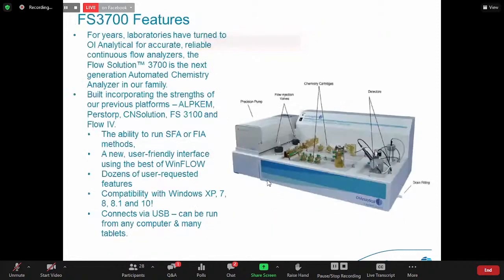the FS 3700. Here's a picture of the current offering. FS, if it's for cyanide, this might change to CN 3700. It's an advanced continuous flow analyzer designed to improve laboratory productivity and wet chemistry test procedures. So here on the left, you see the autosampler, the pump, and the chassis of the instrument. And we're going to go into the various bits and pieces that make up this instrument.